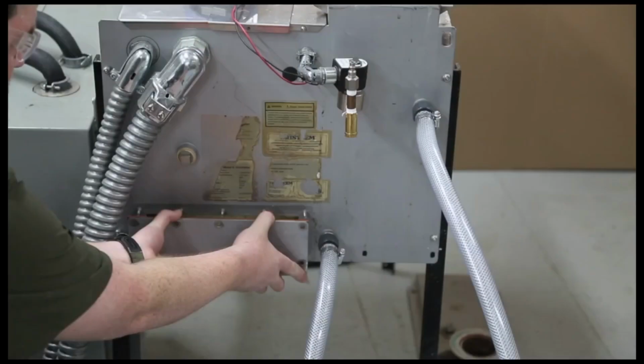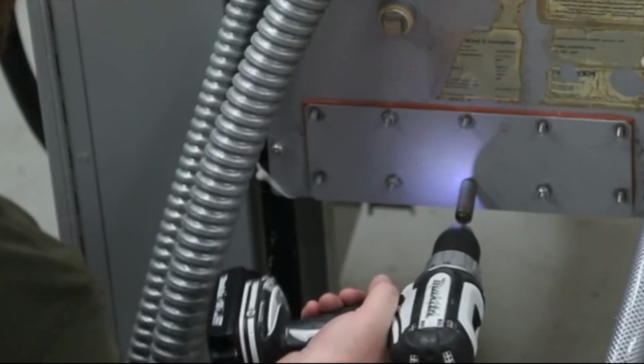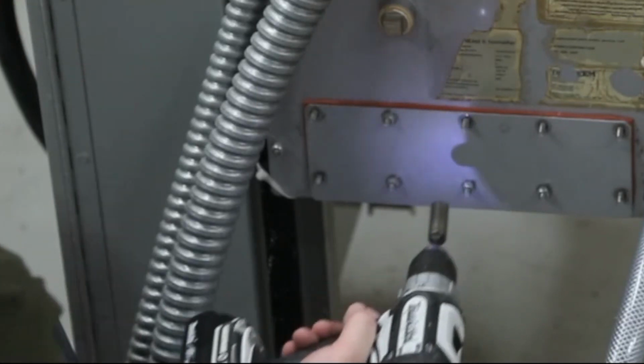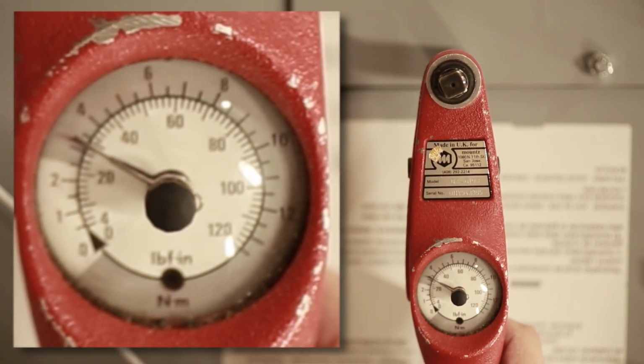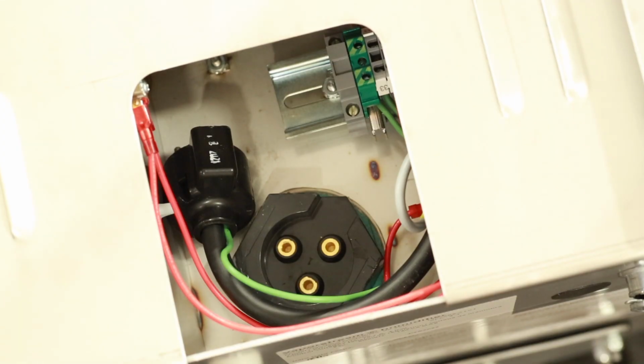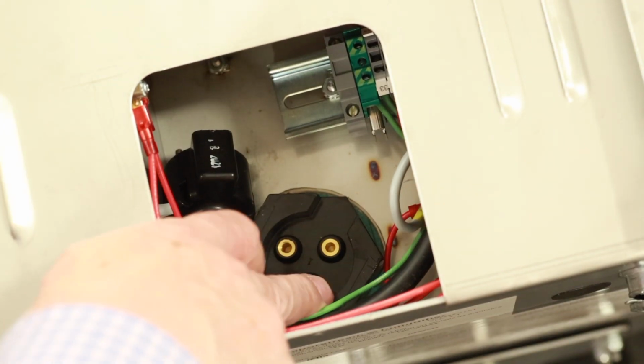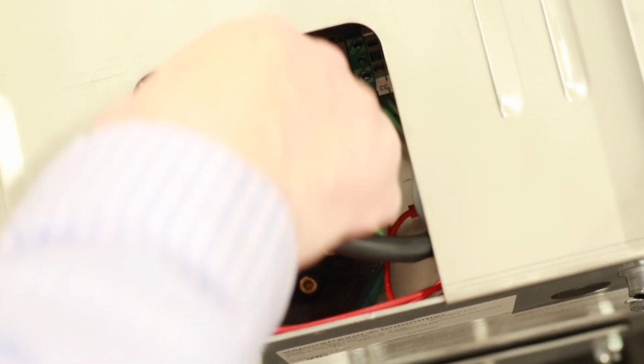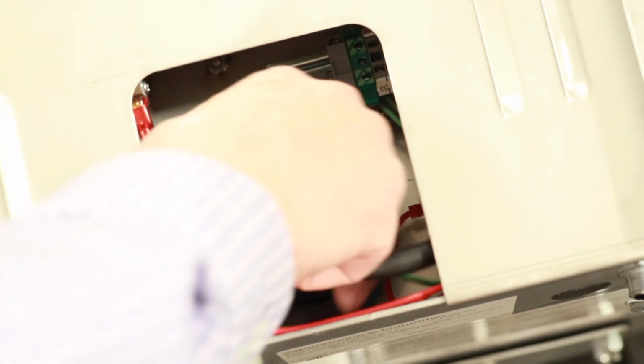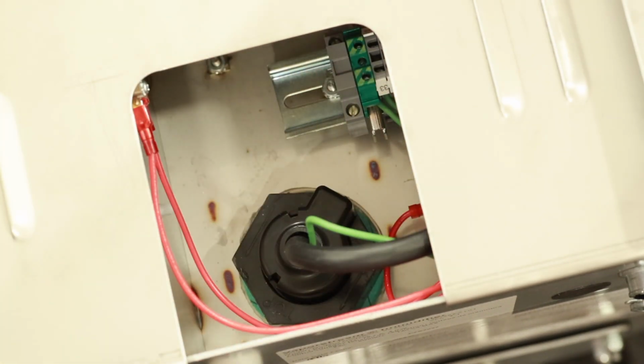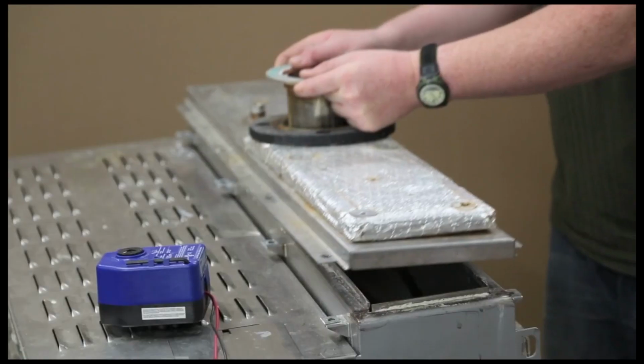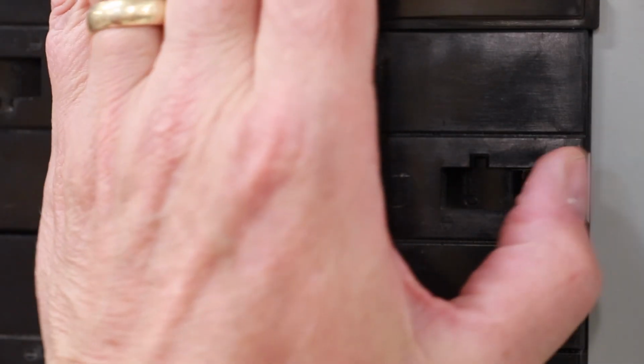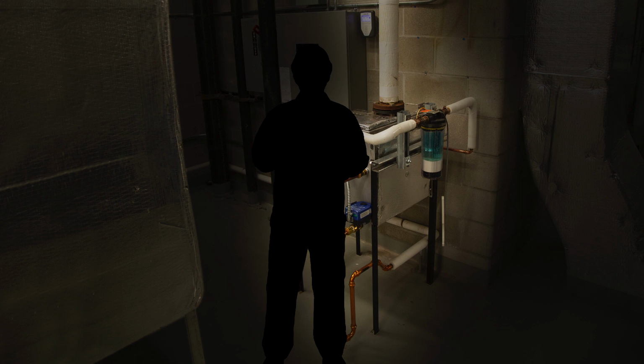When the maintenance requirements are complete, slide the cleanout tray back inside the tank and slide the cleanout plate over the tank studs. Torque the cleanout plate nuts to 25 to 35 inch-pounds. Verify that the probe rod holder is secure and that the probe plug and cable assembly are plugged into the probe rod holder. Replace and secure all covers and doors. Turn on the electrical power, and do not leave the humidifier unattended.